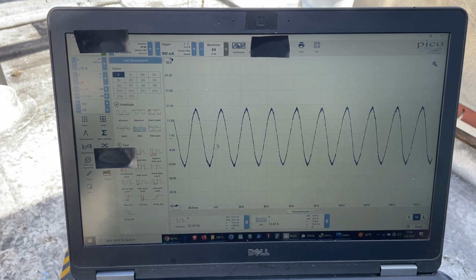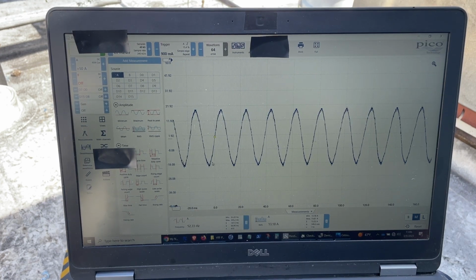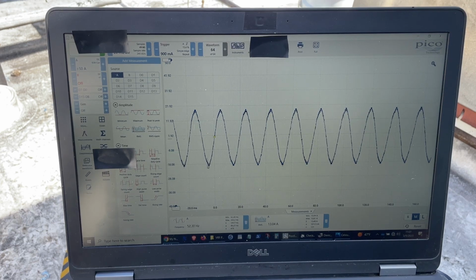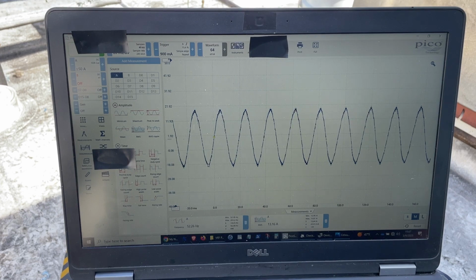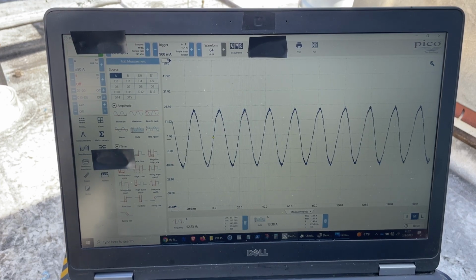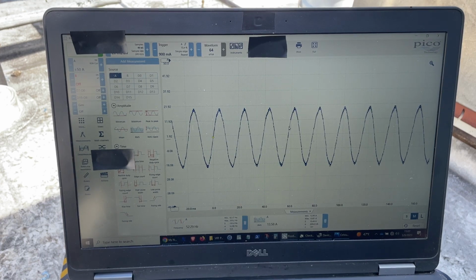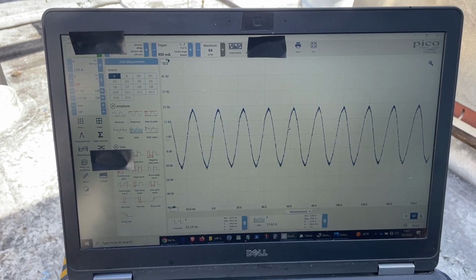Might have kicked on the standard. The way these work is the inverter always starts up first, then goes to max capacity, and if it still needs more capacity, it will kick on the standard. When it does that, the inverter drops back down. Then as the unit gets closer to satisfying, the standard will cut off and the inverter will then shut down. The inverter is always the first to cut on and the last to cut off.